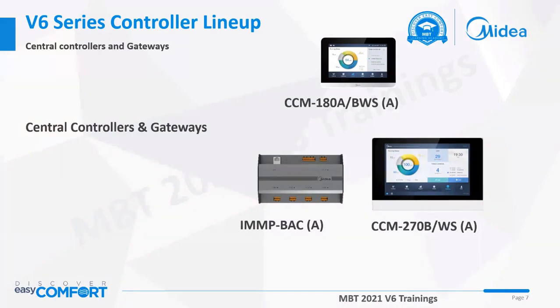This one only has one XYE port, so it can connect 8 systems or 64 indoor units. This one has 6 XYE ports, and each port can connect 8 systems and 64 indoor units. So maximum 8 multiplied by 6 gives 48 systems and 384 indoor units that can be controlled by the bigger 10.1-inch touchscreen.